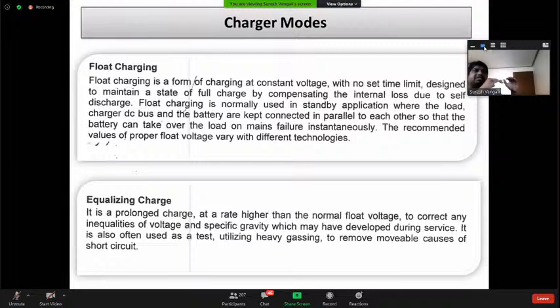But equalization charging means when you need it after a power loss - you feed through battery, then when power comes back, the battery has already depleted 30-40%, so you need to recharge the battery immediately. So you need high rate charging - they will constantly send a high current to bring the battery back to normal position. That is the reason they do it.